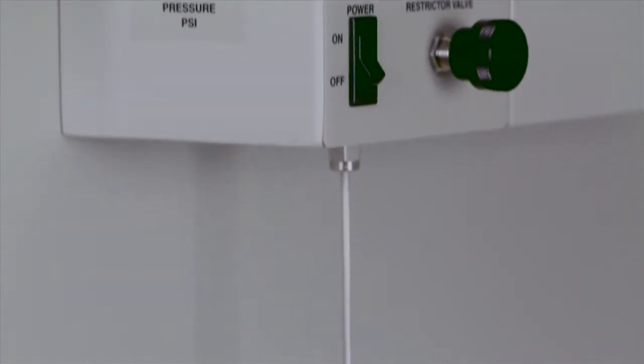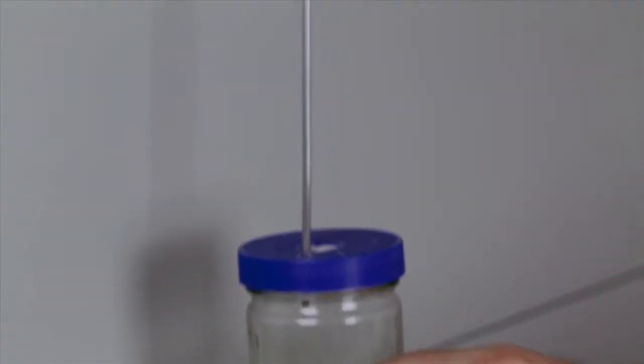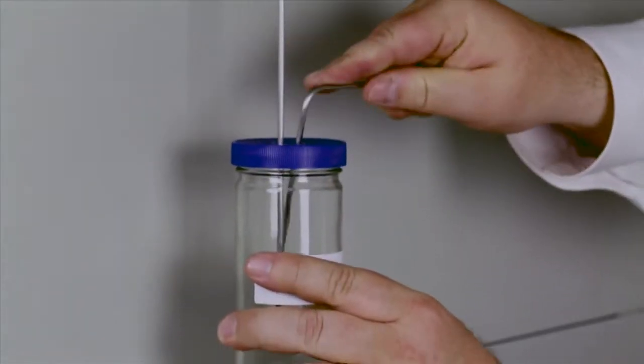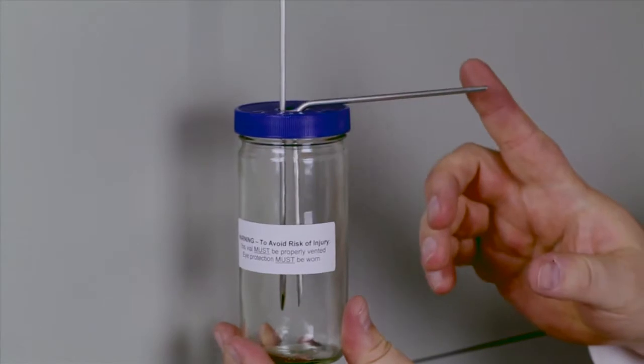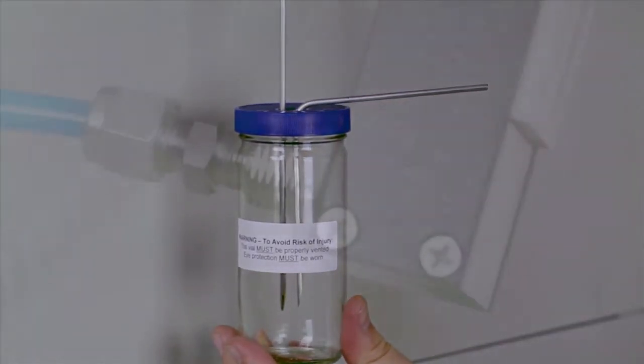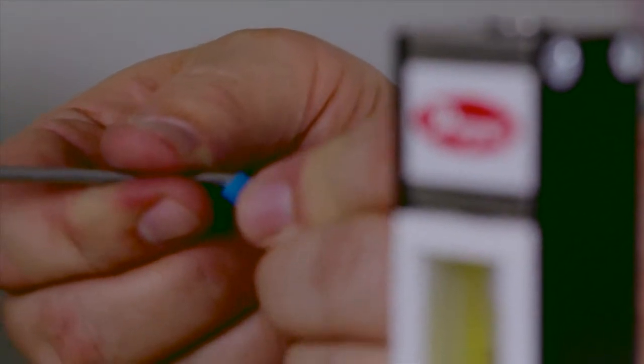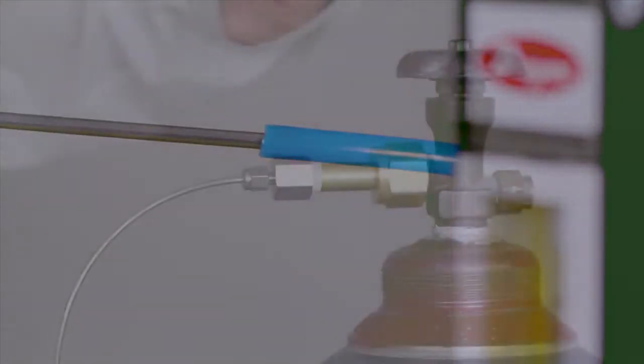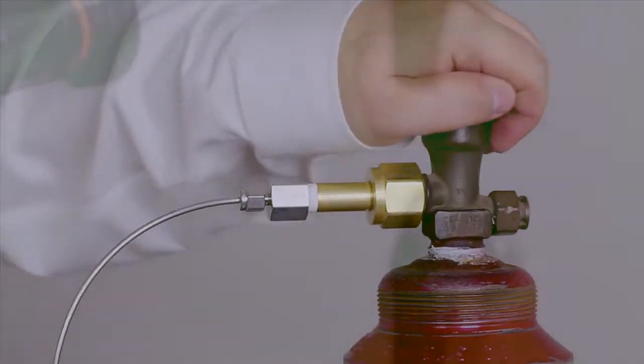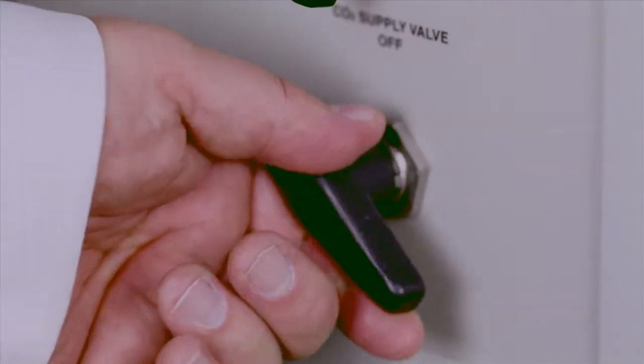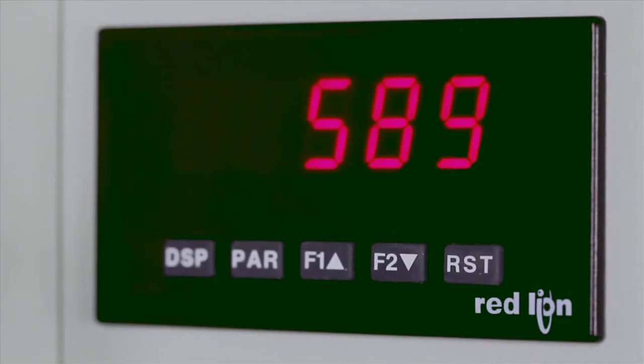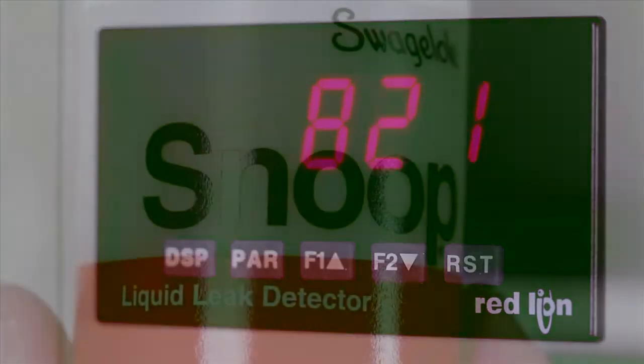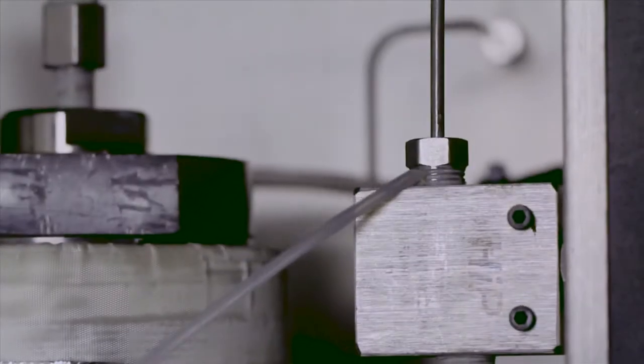The extract may be collected in an EPA-style septa vial or container of your choice. If a septa vial is used, it must be vented. If the optional flow meter has been purchased, connect the outlet from the septa vial to the flow meter as shown here. Open the CO2 tank and the CO2 inlet valve, allowing the system to equilibrate to tank pressure. Use Snoop or another leak detector to ensure all connections are tight.